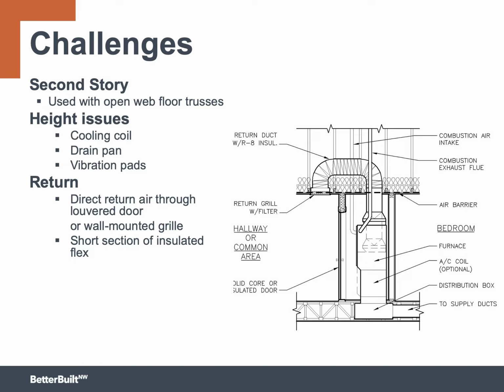Even though we're talking about ducts inside, certification programs allow 5% of the length of the ductwork to run outside the conditioned space. That exception was created for just the condition that you see here, where the piece of flex duct goes through the attic. It's a very short run that gives you a little bit of extra sound deadening.